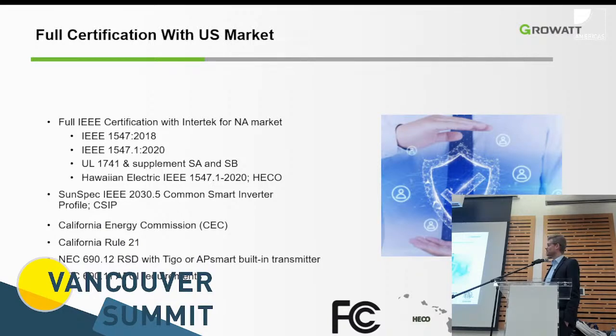The certification part is extremely important, not only the certification we talked about from the battery side of things in the system, if you add batteries to it, but also now with the requirement, as Randall mentioned, to UL 1741 SA and SB. Some jurisdictions in the Canadian market, specifically Fortis in Alberta, are already requesting the SB certification, and we see slowly but surely most manufacturers having SB available. Hoymiles with the HMS series was also one of the first candidates in the market offering SB, and we will see that requirement pretty much going through the provinces, and sooner or later all the provinces will require the SB certification. It also has the communication specification, also part of SB, the 2030.5.